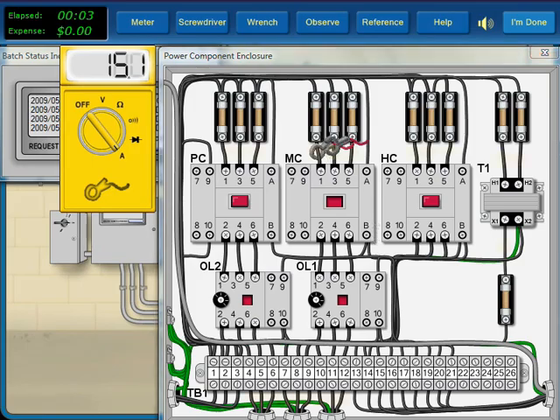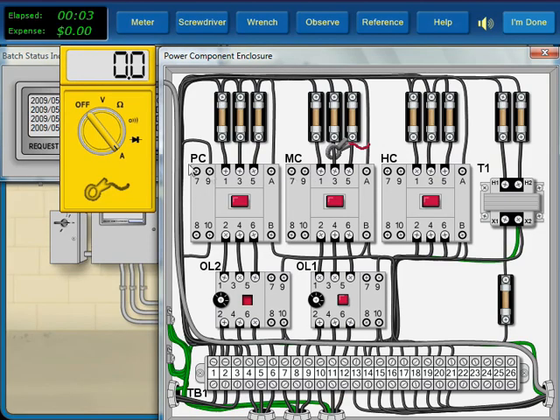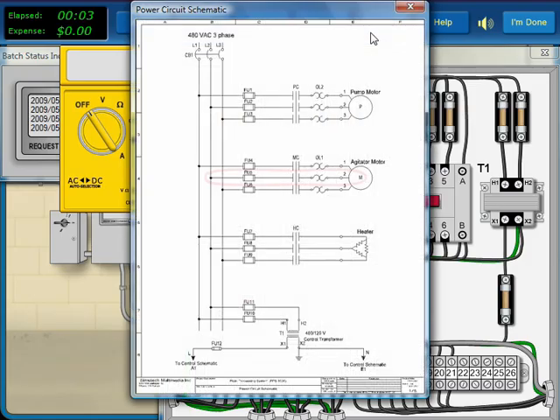We read locked rotor current in two phases, but no current in the center phase. Therefore, there is an open in the center phase.